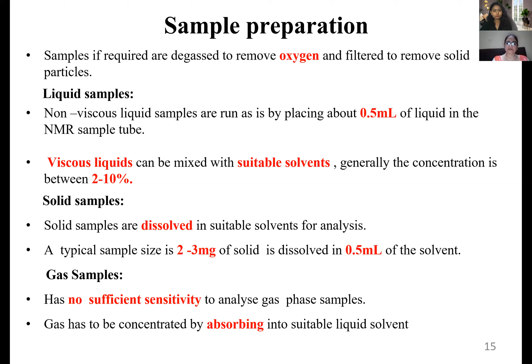The samples are usually liquid samples. If they are non-viscous liquid samples, they are run as is by placing about 0.5 ml of liquid in the NMR sample tube. If they are viscous liquids, then they can be mixed with suitable solvents. Generally, the concentration is between 2 to 10%. If there are solid samples, then they are dissolved in suitable solvents for analysis. The typical sample size is 2 to 3 milligrams of solid dissolved in around 0.5 ml of the solvent. Gas samples have very poor sensitivity, so they are concentrated by absorbing them into suitable liquid solvents.